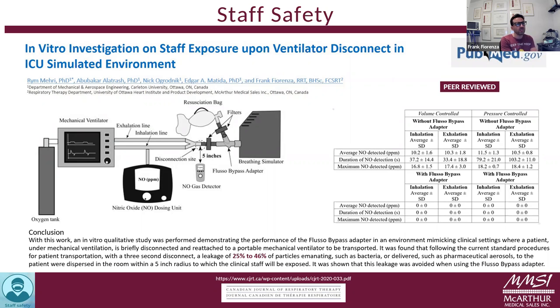Then you can see the little NO monitor, so that sniffed environmental air to determine what escaped from the circuit. If we look at the chart, there was nothing measured when Flusso bypass was used. But when it was not used, on a very brief 3-second circuit disconnect, you had a leakage of 25 to 46%. Now why the range? The range is caused by - instantly 25% was measured, and then after 33 to 37 seconds, that peaked to 46% before it started to come back down. So in short, clinicians are exposed to almost 50% of the dose of nitric oxide in this setup.